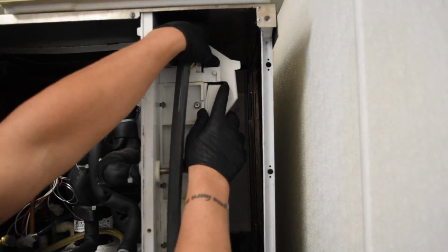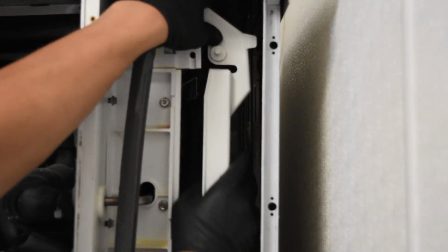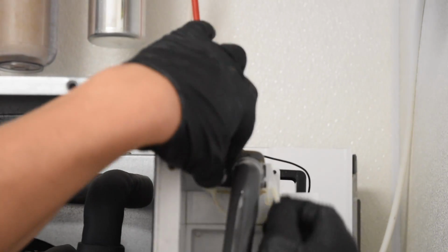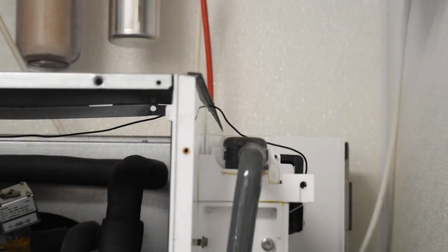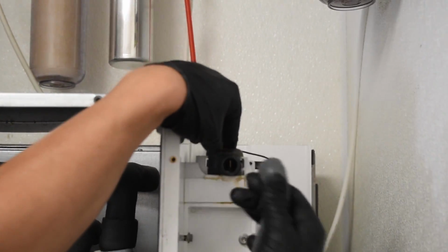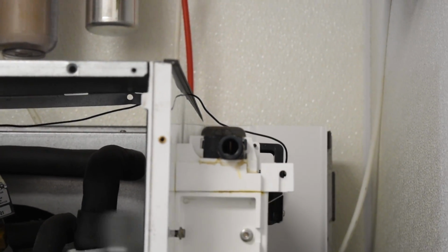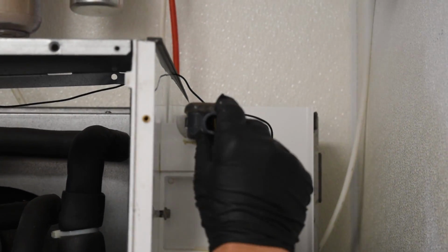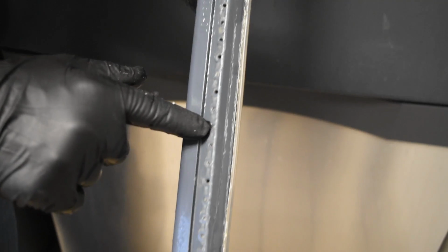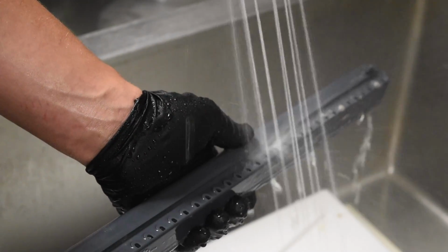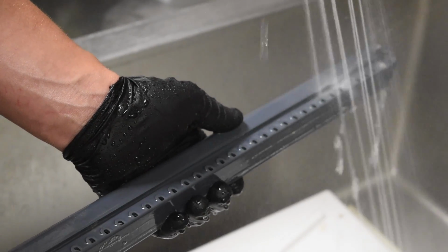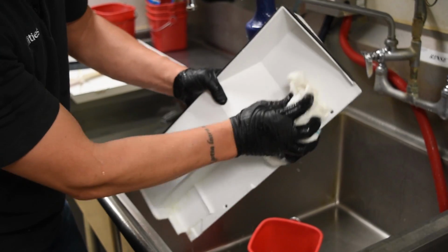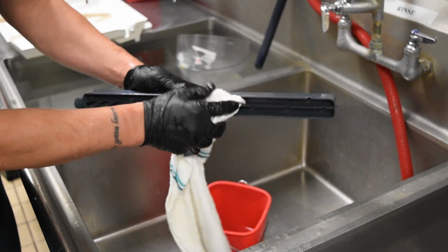Repeating the earlier process, remove the ice curtain. To remove the water distributor head, first twist the hose clip and set it aside. Then remove the hose from the distributor head and pull the distributor forward and then up. The distributor head orifices will be clogged with water deposits and will need to be sprayed off with the rest of the parts. Next, take your sanitizing solution you prepared earlier and thoroughly wipe down all of the parts.